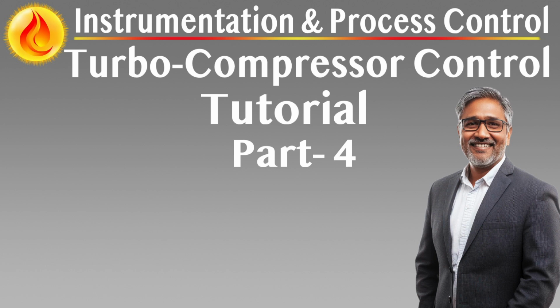Report generation: automated and on-demand reporting for operational transparency, maintenance planning, and performance analysis. Reporting capabilities within the TCCS HMI. The Turbo Compressor Control System, TCCS, includes robust report generation functionality embedded in the human-machine interface, HMI, enabling both operators and maintenance teams to access detailed, structured, and historical insights into the performance, status, and health of the turbo compressor systems. Reports are generated either on demand by authorized personnel or automatically on a scheduled basis and are saved in accessible formats for review, printing, or archival.